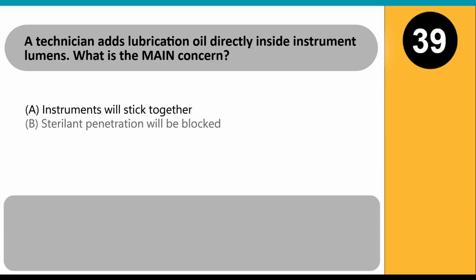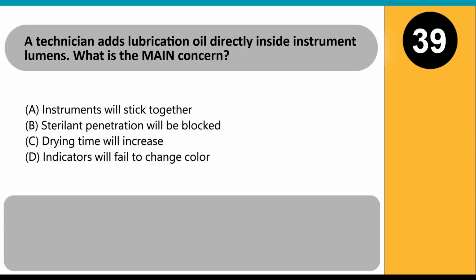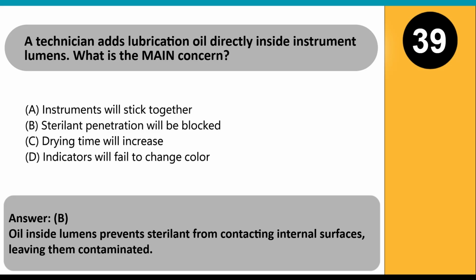A technician adds lubrication oil directly inside instrument lumens. What is the main concern? A. Instruments will stick together. B. Sterilant penetration will be blocked. C. Drying time will increase. D. Indicators will fail to change color. Answer: B. Oil inside lumens prevents sterilant from contacting internal surfaces, leaving them contaminated.